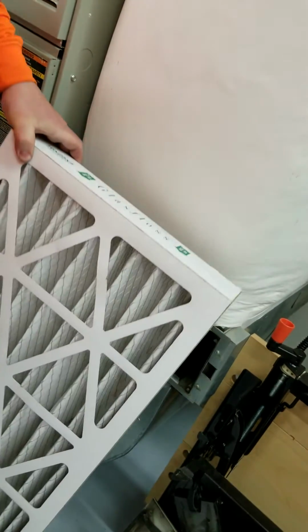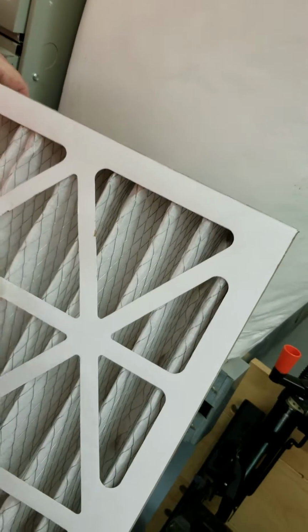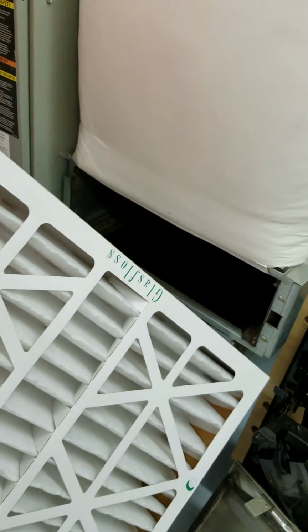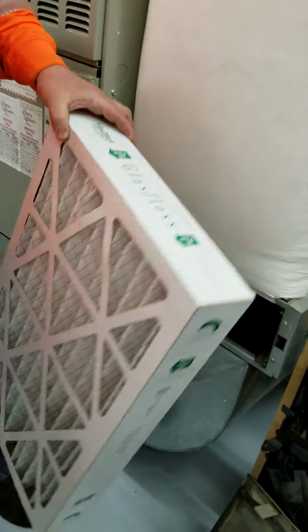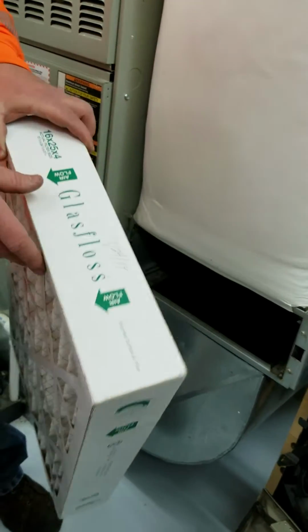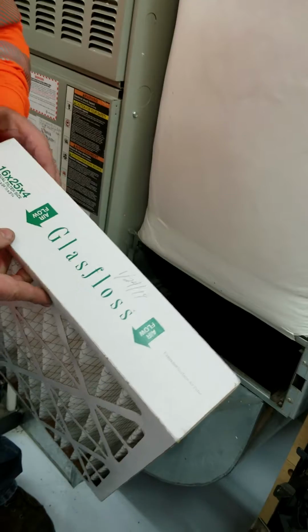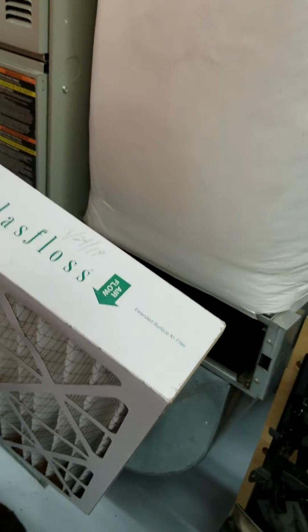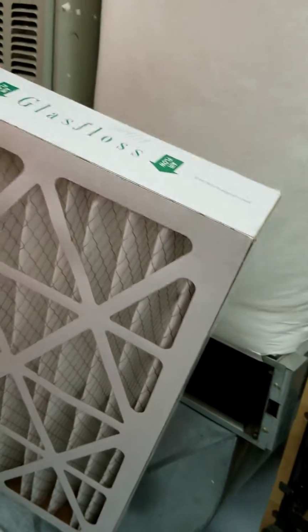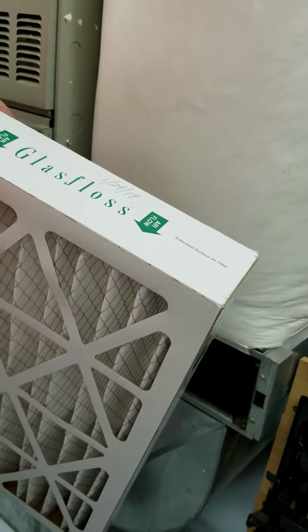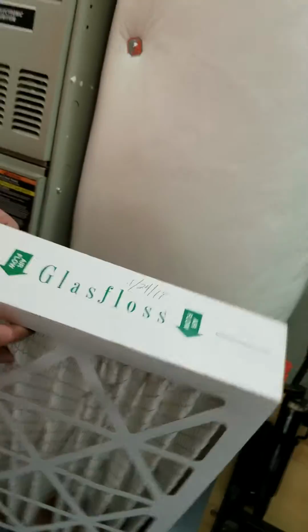If there is no airflow arrow, look for wire mesh reinforcement showing on one side versus the other. The reinforced side always goes towards the furnace. Whether it's downflow or upflow doesn't matter. That airflow arrow always points, if you follow the return duct here, down and into the base of the furnace, towards the furnace. So go ahead and put it in.